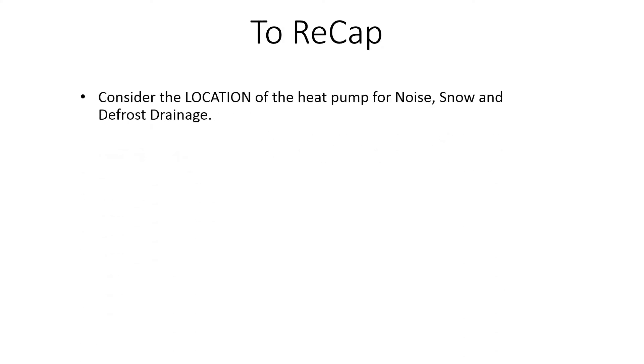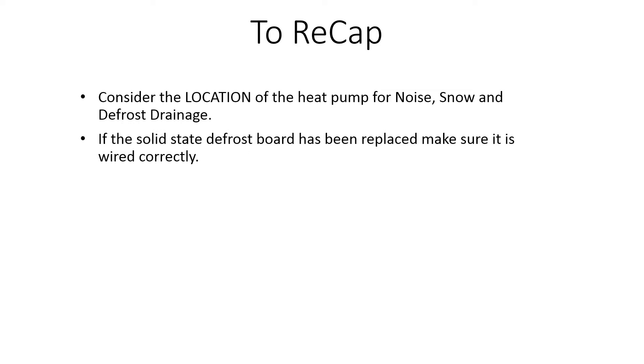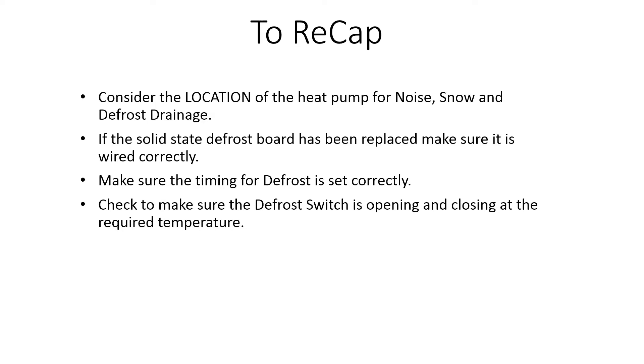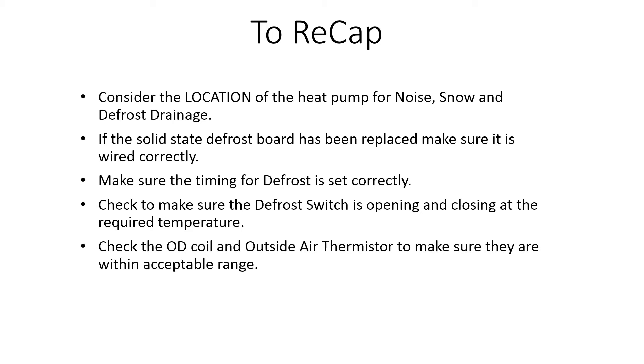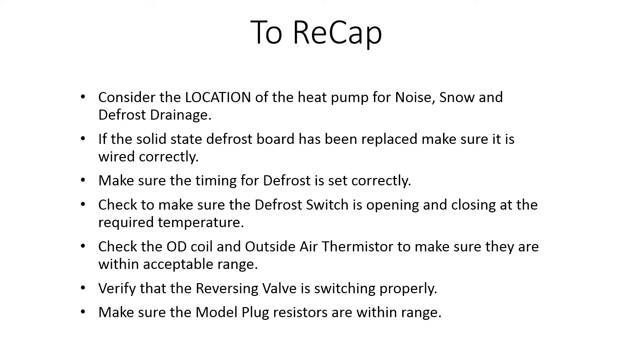To recap: consider the location of the heat pump for noise, snow, and defrost drainage. If the solid-state defrost board has been replaced, make sure it is wired correctly so the timing circuit is powered. Make sure the timing for the defrost is set correctly. Check that the defrost switch is opening and closing at the required temperature. Check the outdoor coil and outside air thermistor to make sure they are within acceptable range. Verify that the reversing valve is switching properly, and make sure the model plug resistors are within range.